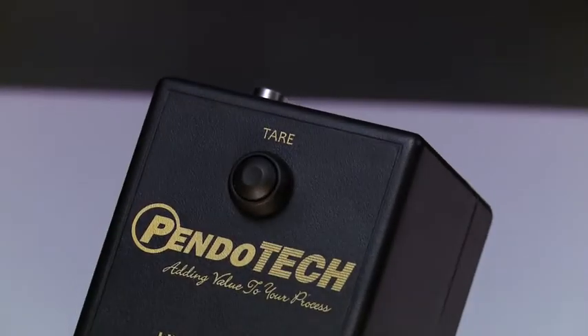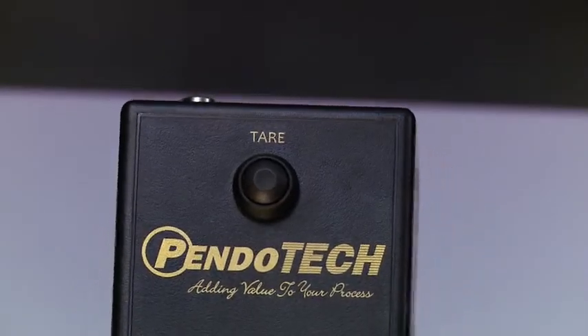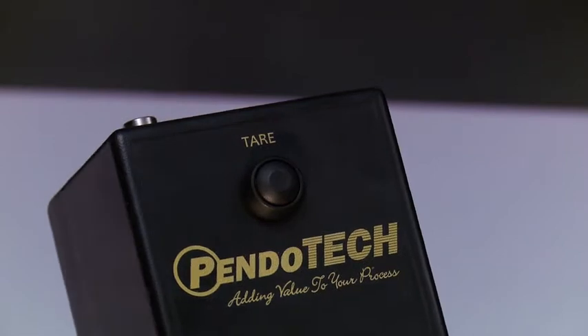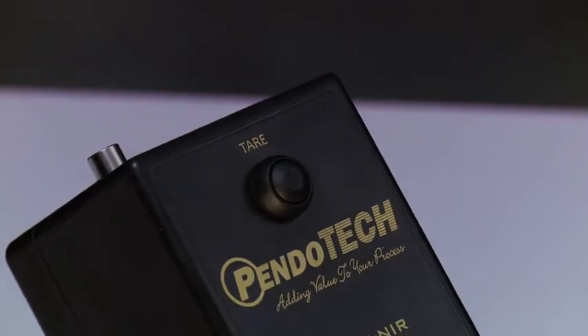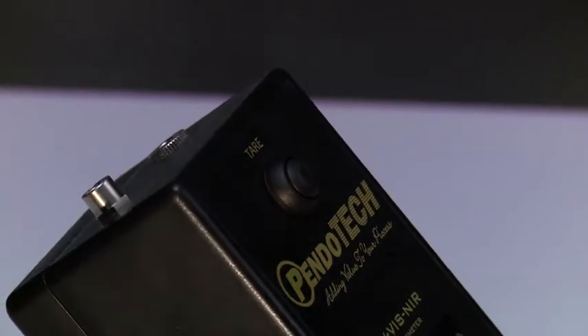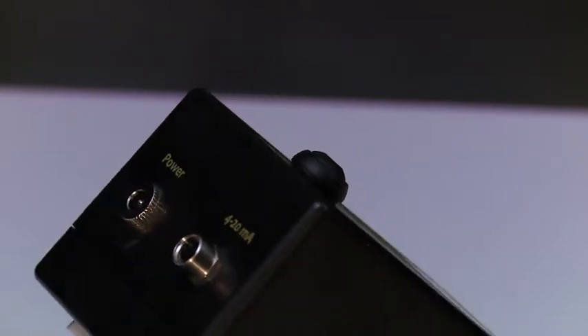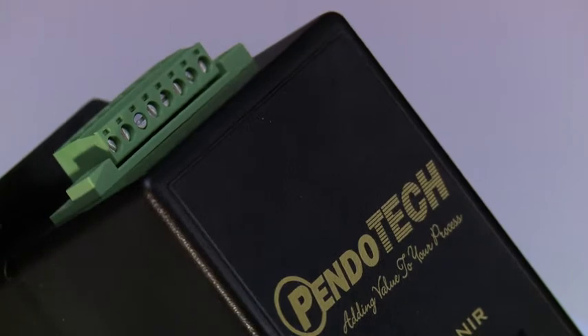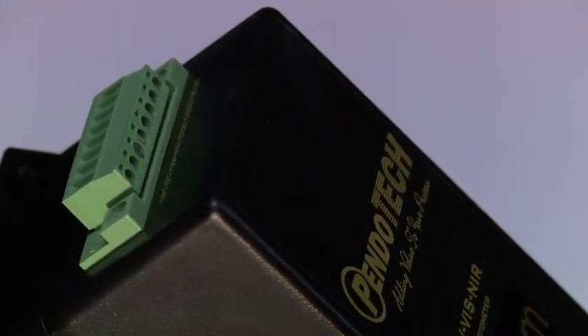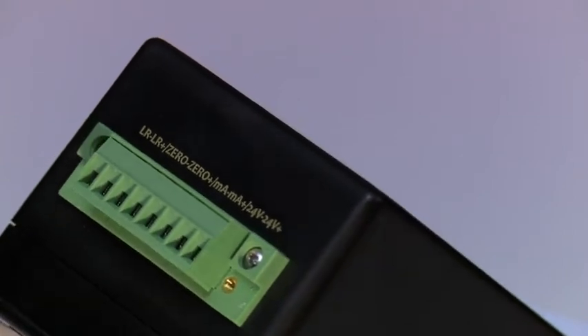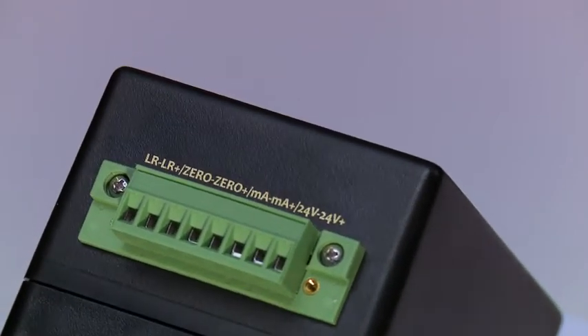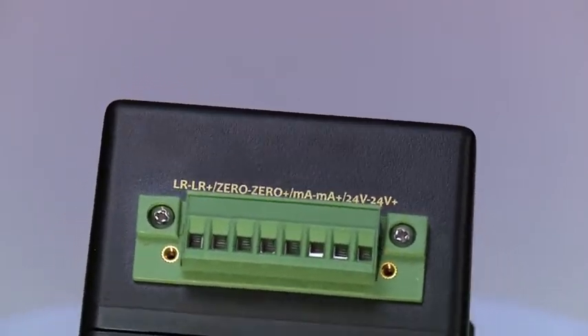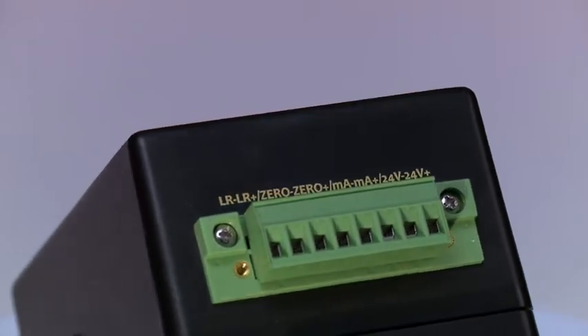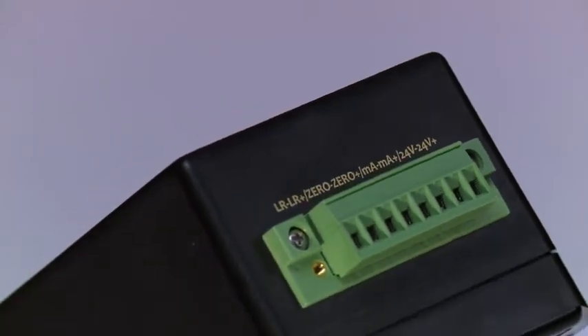The photometer has a tare input that sets the baseline absorption, as determined by the user, to 0 absorbance units. This would also correspond to 4 milliamps on the transmitter output. For remote mounting inside an industrial cabinet, all electrical signals reside on a screw terminal connector: the power, the output signal, and the tare input.